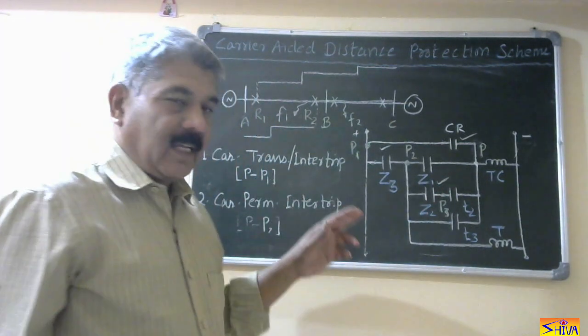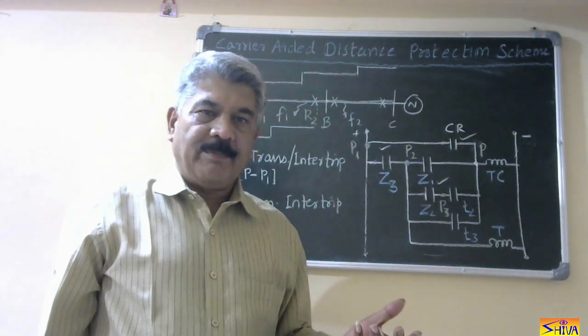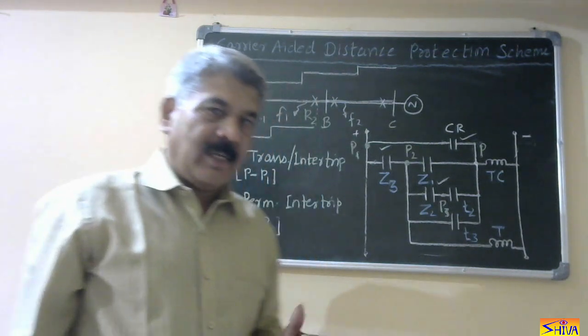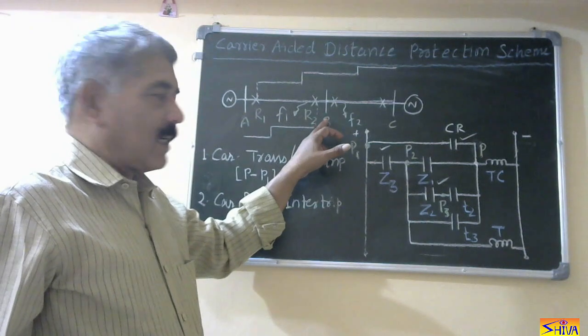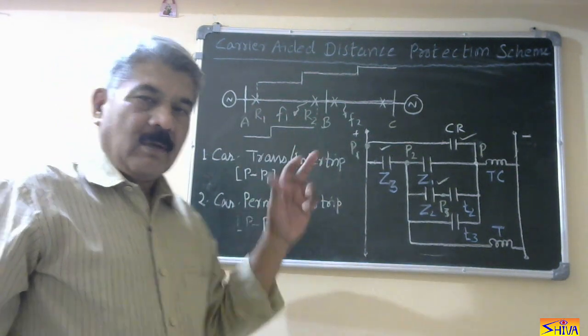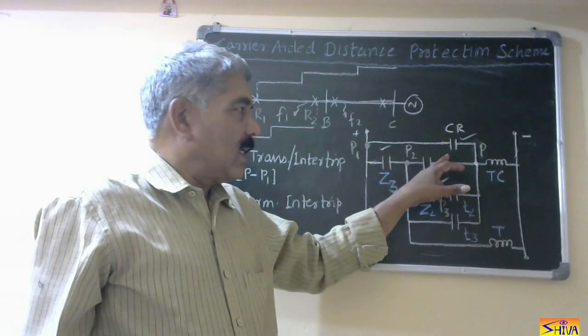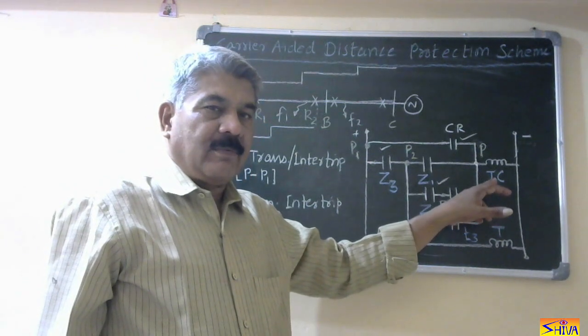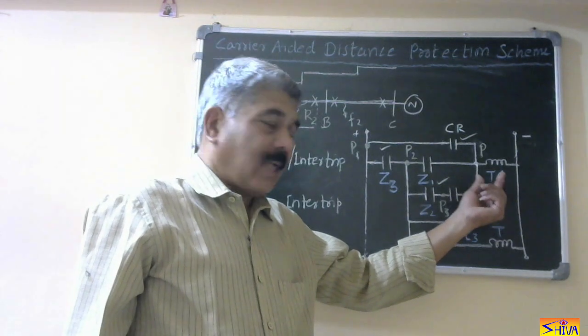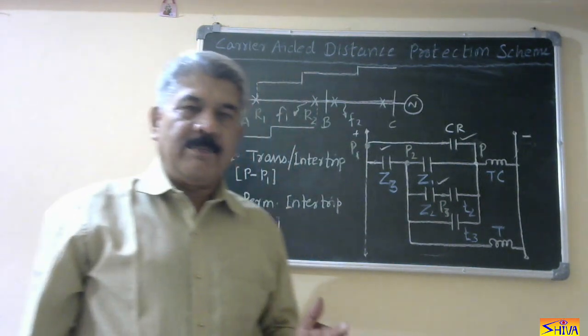So this is the carrier transfer or carrier intertrip scheme. Advantages: circuit breakers at both ends operate simultaneously, therefore there is immediate fault clearing and the transient stability of the system is improved. Drawbacks: first, carrier signals are transmitted over the faulty line. Second, due to a noise signal generated by a fault anywhere in the power system, if the carrier receive relay operates erroneously, there will be unnecessary tripping of the circuit breaker at R1.